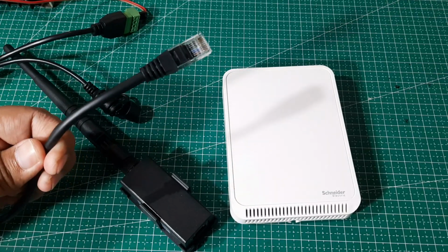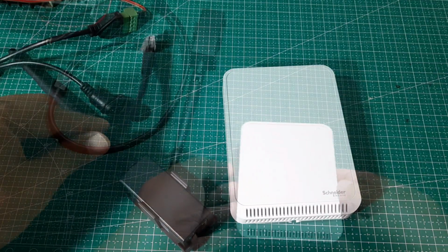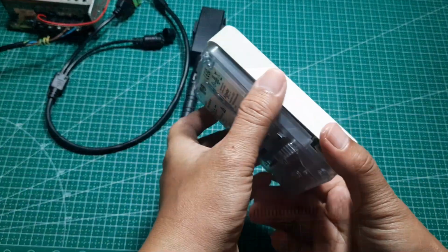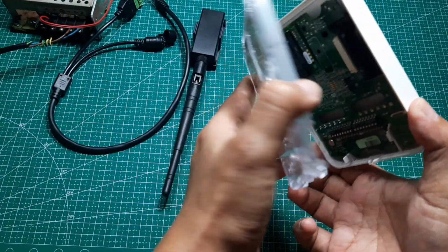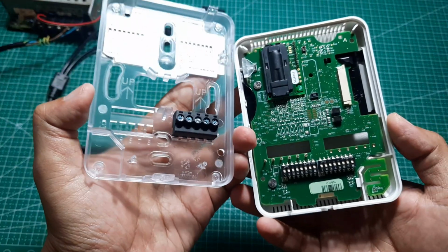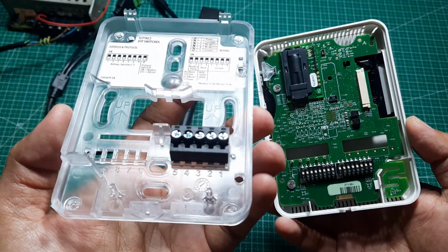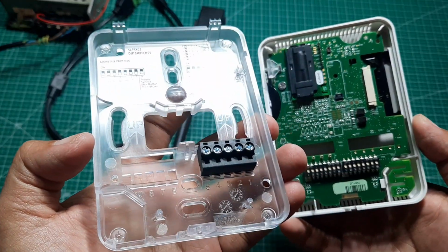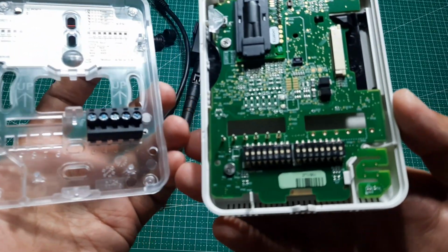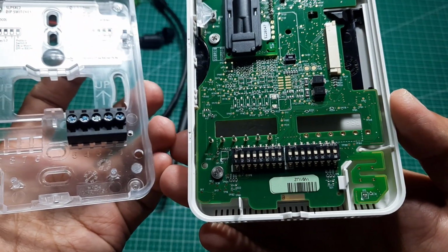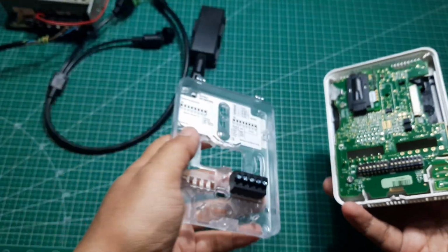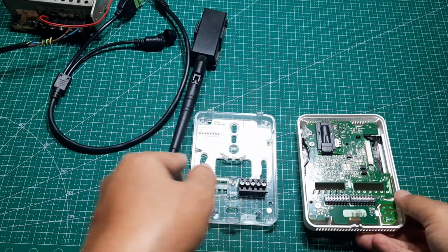For cable installation, first remove the cover from the base at the bottom of the device. Inside, you'll find terminal pins for connecting the 24-volt power supply, as well as pins for the RS485 communication line, which we will connect to the RS485 to Wi-Fi adapter. There is also a DIP switch for configuring the device address and communication settings.